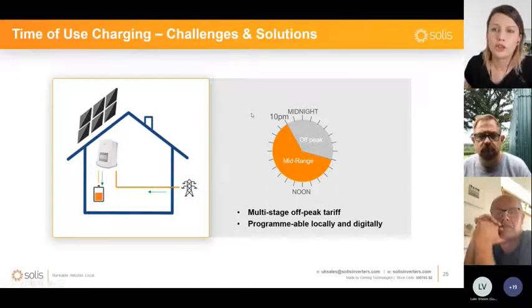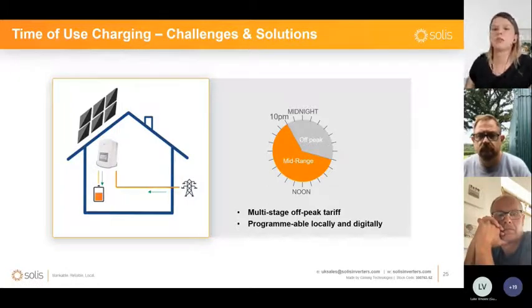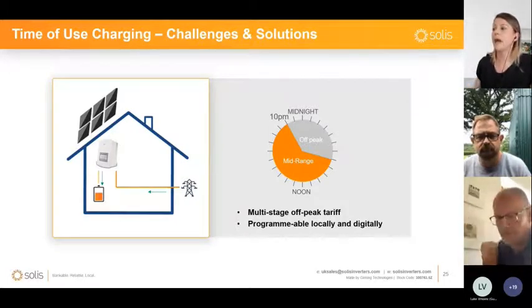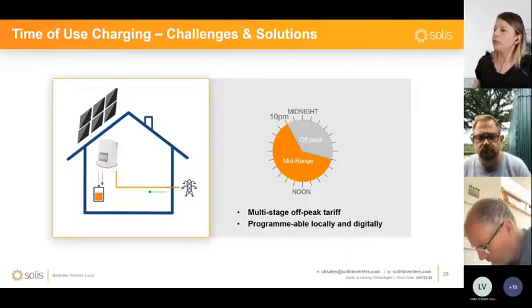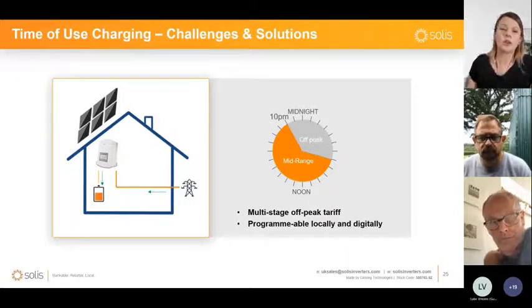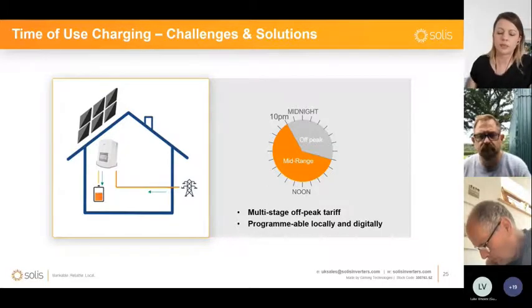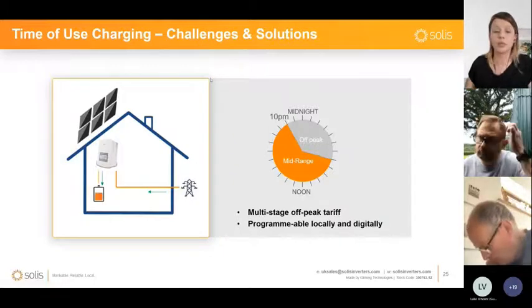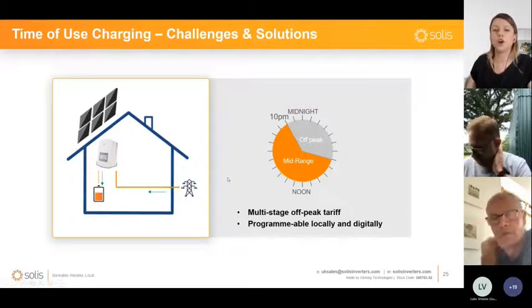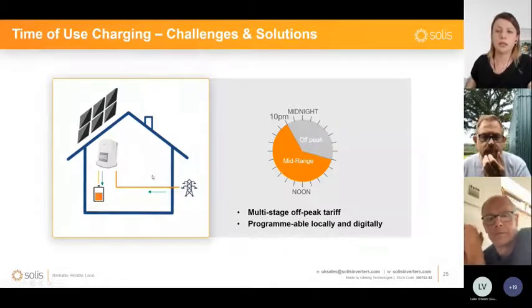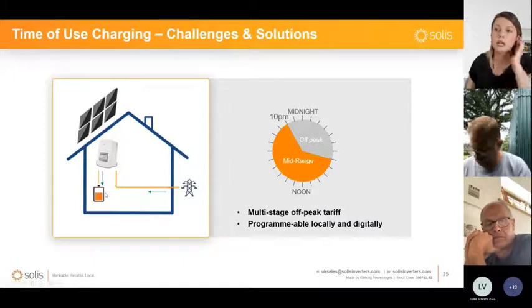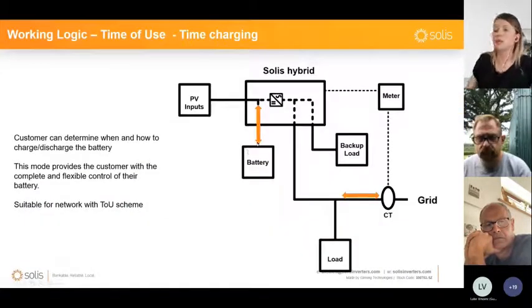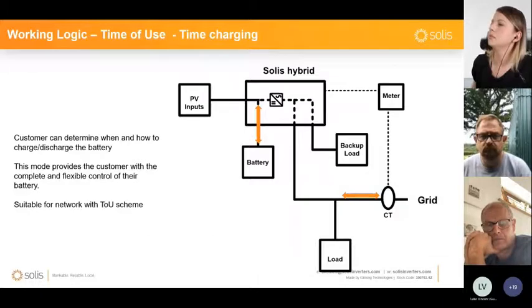The next working logic for time of use can also work in parallel with the self-use mode. If the customer has multi-stage off-peak tariffs, they will be able to program the inverter. For example, if they have a lower tariff during nighttime, they're going to be able to charge their battery during nighttime and use that energy during times where higher tariffs are applied, for example in morning time or in evening time.